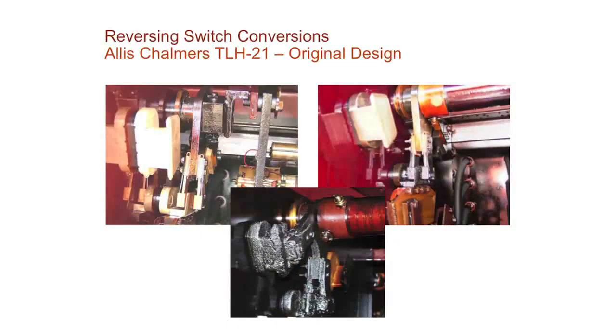Talked about the Allis-Chalmers. This is the original design. You can see discoloration here. This is what I was referring to when I was talking about the coking. This is what it looks like inside the unit. Basically, it's built up. When that leaves position and comes back, it's hard for that to make a clean connection. So what we've done, we've gone in and this is the original design. You can see you have flat blades here. You can see how it just rides on the surface, and when that coking builds up, it basically starts separating those contact points. Then you get more arcing, then you get more coking is the phenomenon that happens.